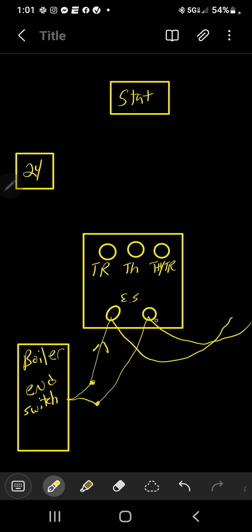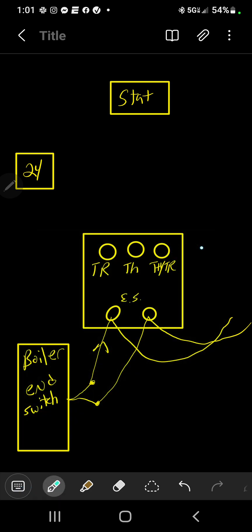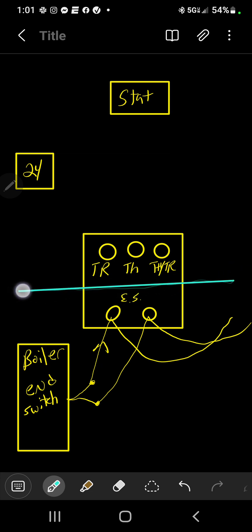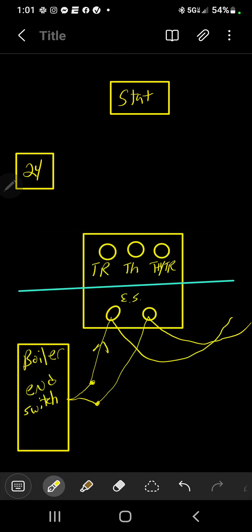Now you can picture this zone valve, let's draw a line here and change the color. Picture this zone valve being kind of cut in half. You got your 24 volts down here for the end switch. Now up top here you also have a 24-volt, a separate transformer. You're going to send 24 volts into this transformer here and over here.